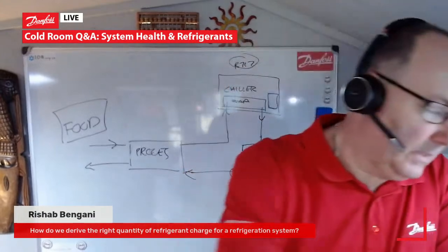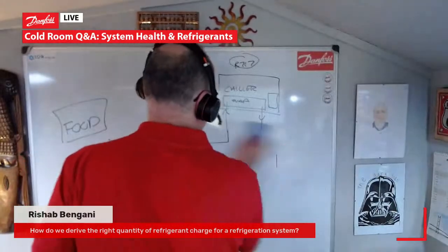How do we derive the right quantity of refrigerant charge for a refrigeration system? Yeah, that's a very good question. Charge is an interesting discussion, and I'll just clean that off there. When we talk about refrigerant charge, basically you can estimate the charge of your system by the length of the liquid line and the size of that liquid line. That will give you a base quantity, if you like. Then also take the volume of your receiver, and that will give you an indication of the amount of refrigerant that you will need in that system.